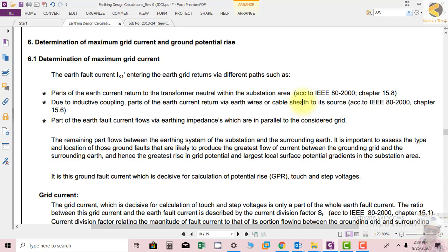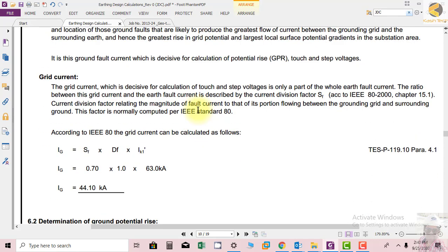Just as a motor designer identifies the hottest part and designs the machine based on that hot spot, we must design our grounding grid based on the maximum grid current to ensure safe operation. The ground fault current is the decisive parameter for calculating ground potential rise, touch potential, and step potential — the three key parameters in grounding design.